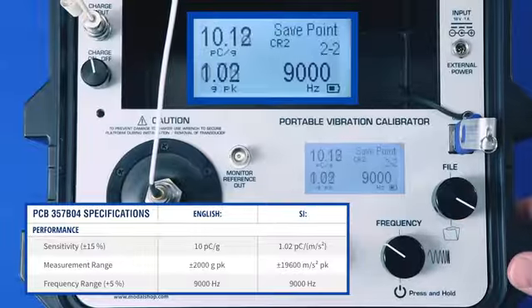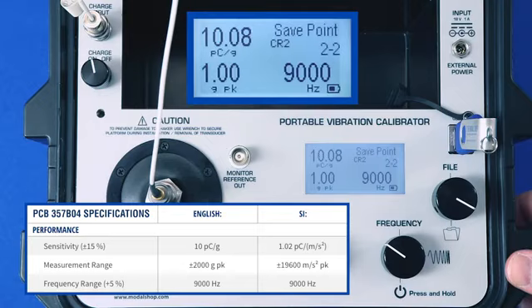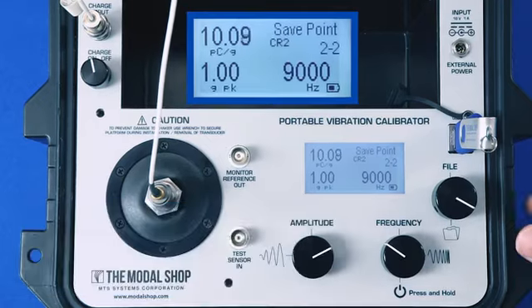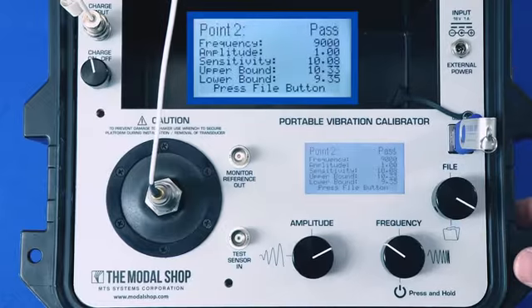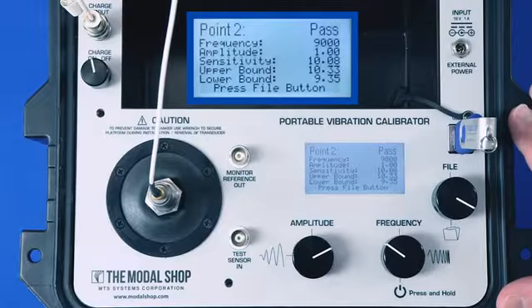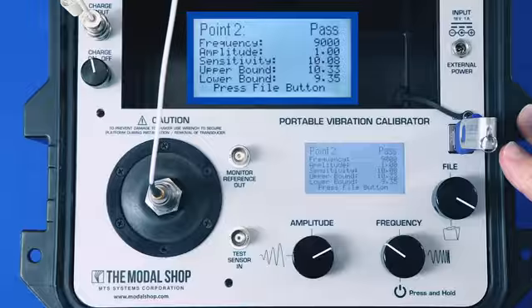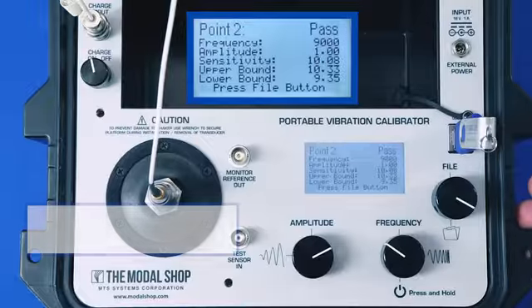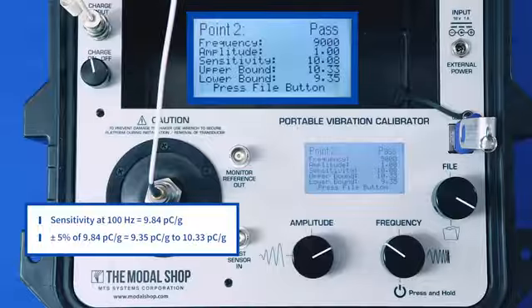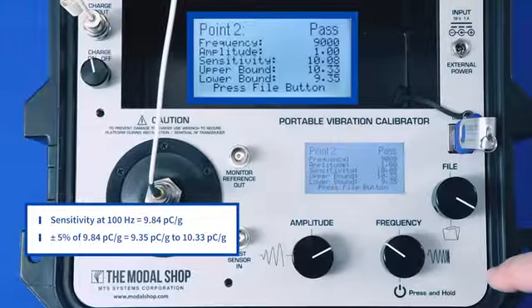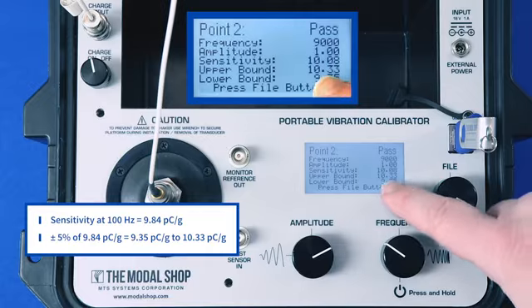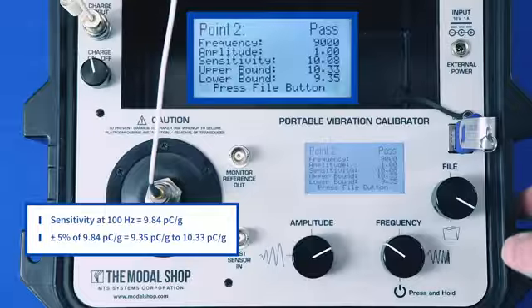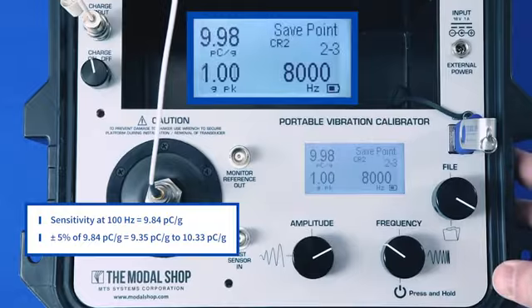Now I'm going to sweep down starting at 9,000 Hertz, and you can see the frequency is automatically adjusted to 9,000 and my amplitude is 1 G peak. The sensitivity is 10.08 picocoulombs per G. Now what the calibrator will do is apply a plus or minus 5% tolerance. The rest of the frequency points have a plus or minus 5% tolerance, so I've programmed that tolerance, and it will apply that to the sensitivity at my reference frequency. And my reference frequency was that 100 Hertz test point. So I'm allowed to be between 9.35 and 10.33 based on the measurement that I took at 100 Hertz. And that test point passes.